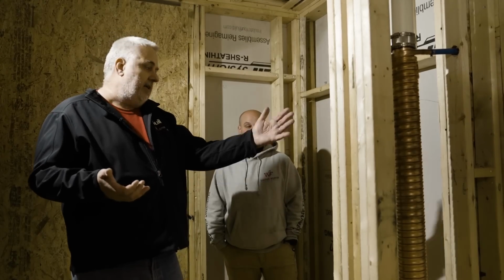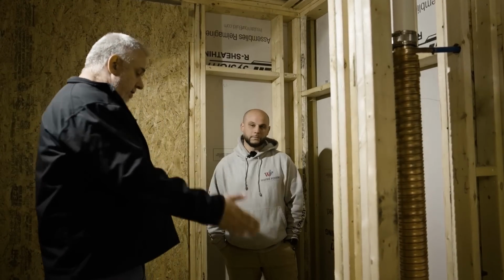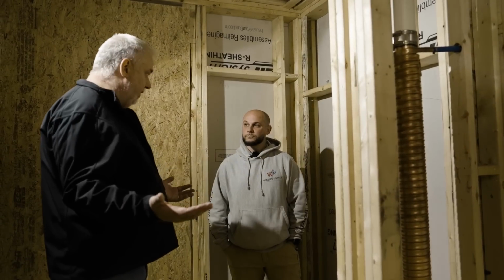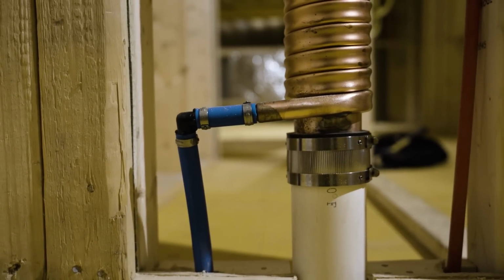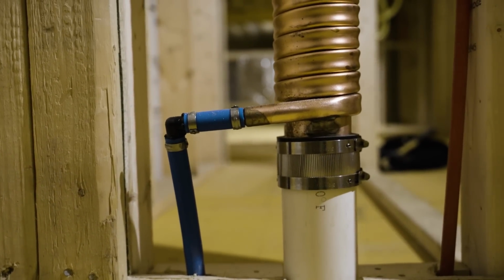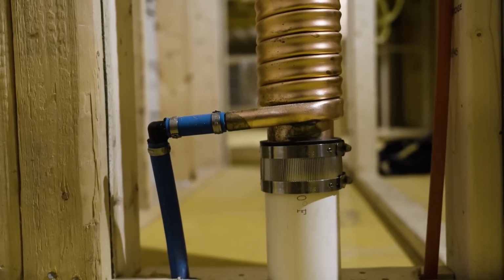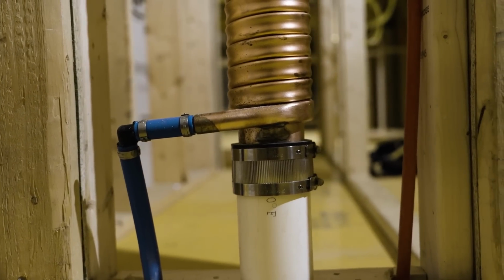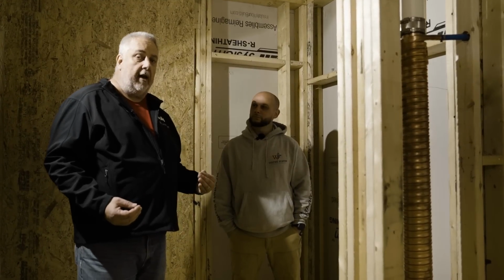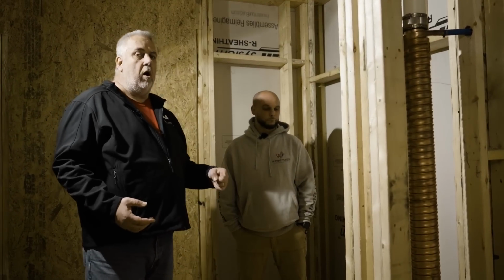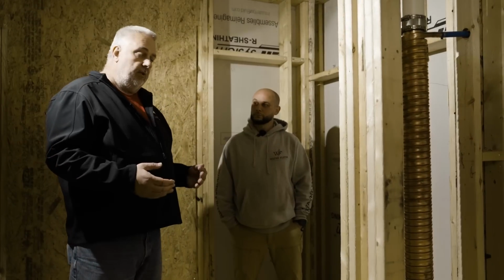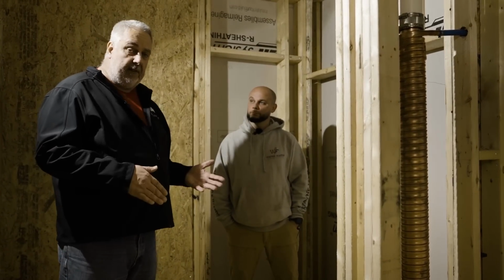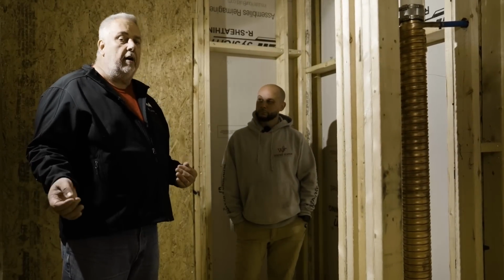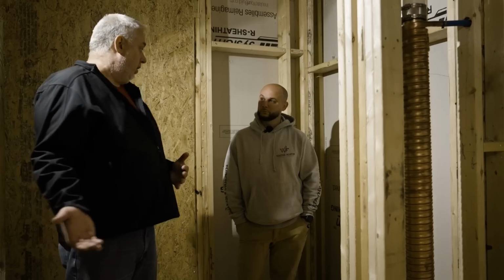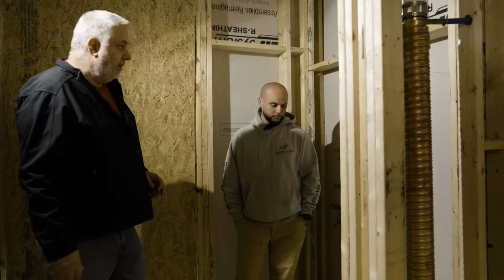Right, so by the time it gets here, maybe it's 90 degrees. Right. And the cold water coming in, I'm guessing it's probably 55-ish. Around there, yeah, plus or minus, depending on the time of the year. So it's a 40-degree delta. But before we let that water go down into the drain and off into the septic system, we're trying to strip off as much heat as we possibly can and put it into that water supply that's going into the water heater, so that maybe that water going in isn't 55 degrees, maybe it's 62, 65 degrees, so the water heater has to do a little less work. Correct, and save energy there. And as well, save energy. So there you have it.